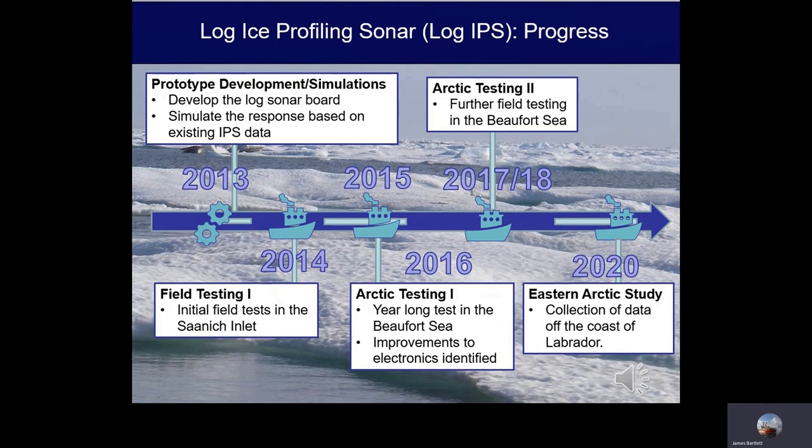Development of the log IPS started in 2013. We initially started looking at data that had been recorded by the traditional IPS-5 and simulated what it would look like on the log IPS. In 2014, we did some testing in local waters around Vancouver Island in British Columbia. And then in 2015, 2016, we had it out in the Arctic for its first ice measurements in the Beaufort Sea.